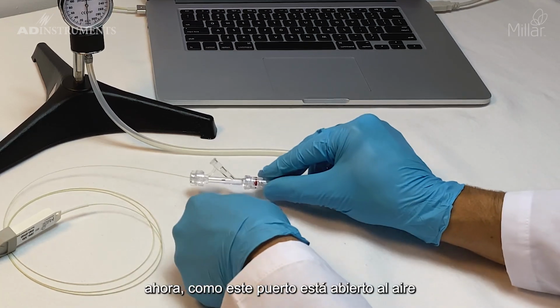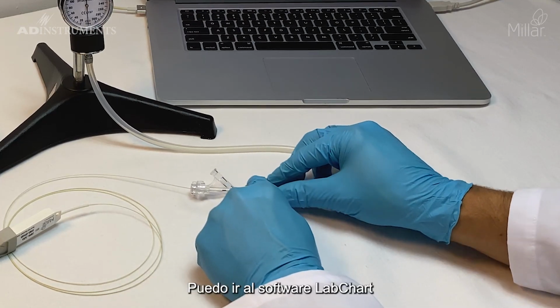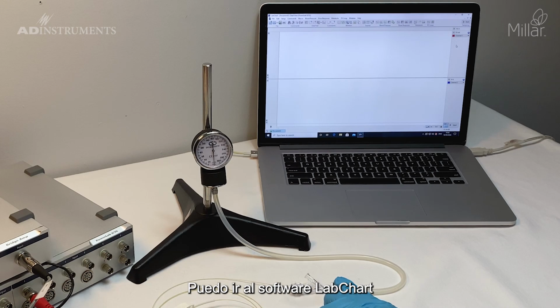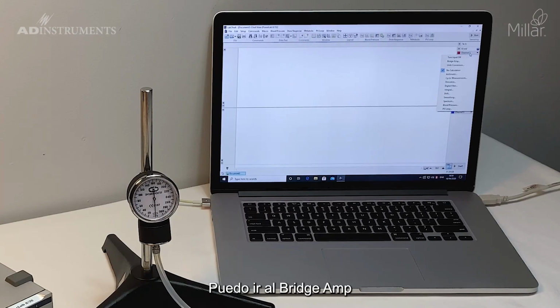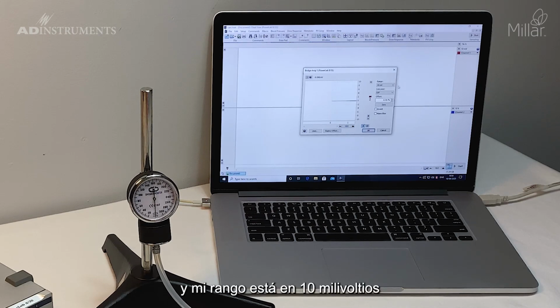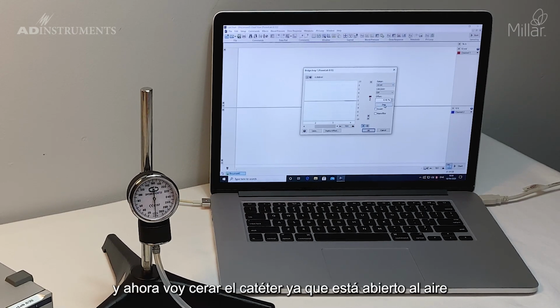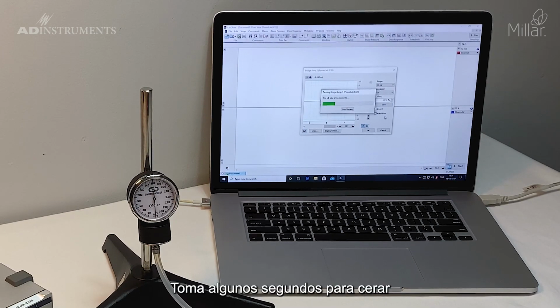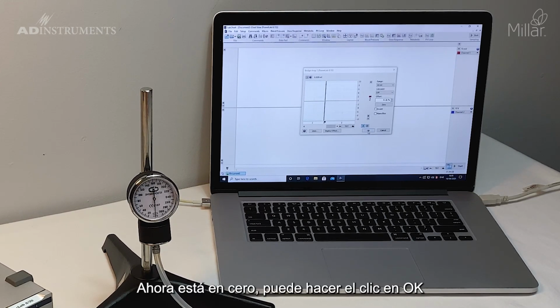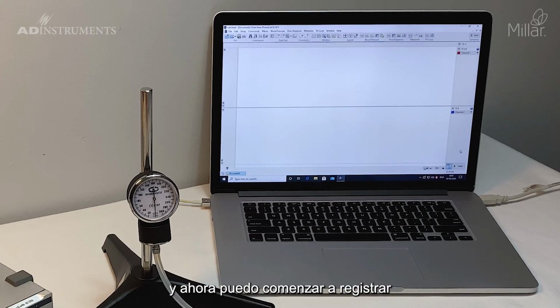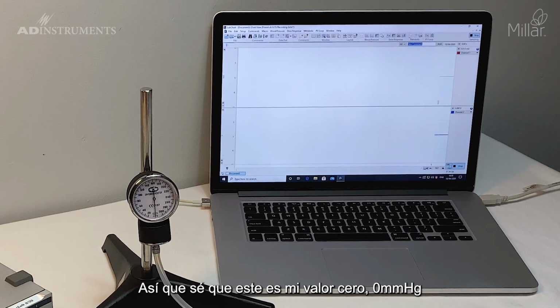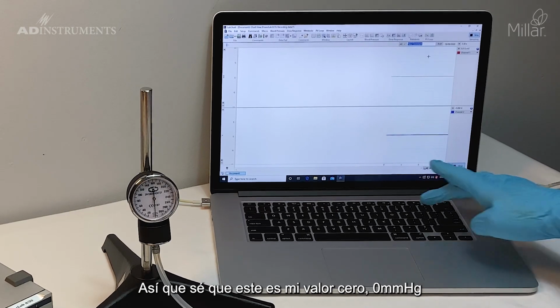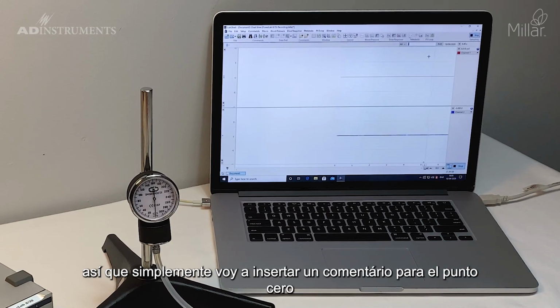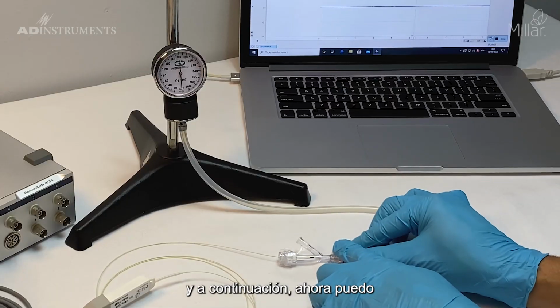Now, because it is open to air on this port, I can go to my LabChart software. I can go to bridge amp, and my range is on 10 millivolts, and now I'm going to zero the catheter as it is open to air. It takes a couple of seconds to zero it. Now it's zeroed. I can click OK, and now I can start recording.